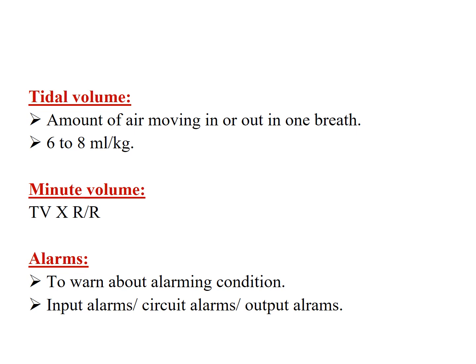So there are different types of alarms: the input alarms, the circuit alarms, the output alarms. There is an alarm which would tell you if the FiO2 being delivered is right or not, if it is high or low. There is an alarm that would give you knowledge of the pressures, if it is appropriate or is it high or is it low. Same is with the respiratory rate and the tidal volume. And in the newer machines, there is an alarm for the end tidal CO2 as well.